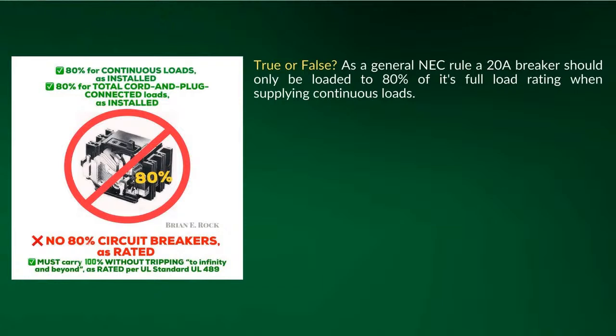But we had some really interesting comments, and basically the equation that I set up was, and I've done this a bunch of times, so everyone that knows me from all the groups knows: you have a refrigerator, a garbage disposal, and a dishwasher, and the combined load is 17.7 amps. Can you put that on a 20 amp breaker? The answer is absolutely yes, you can, because those loads are all non-continuous loads.